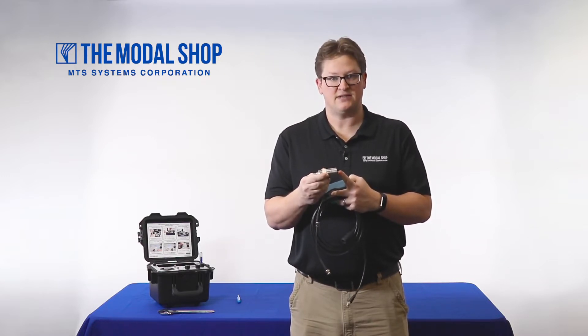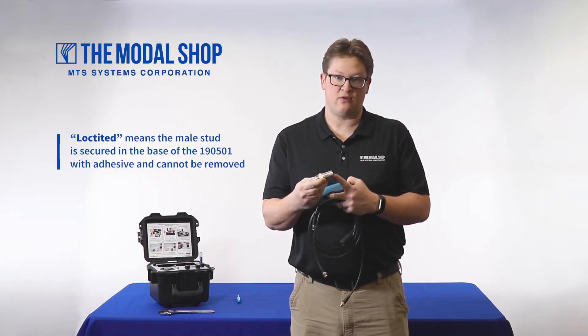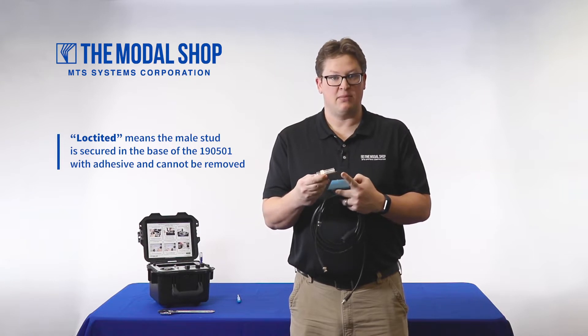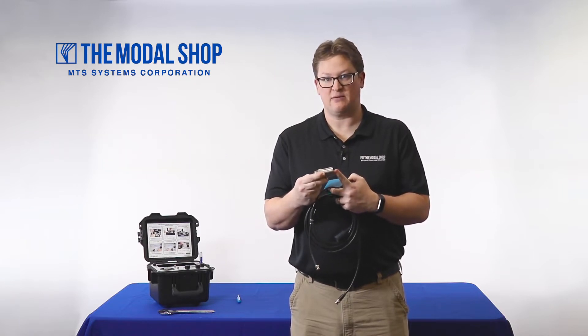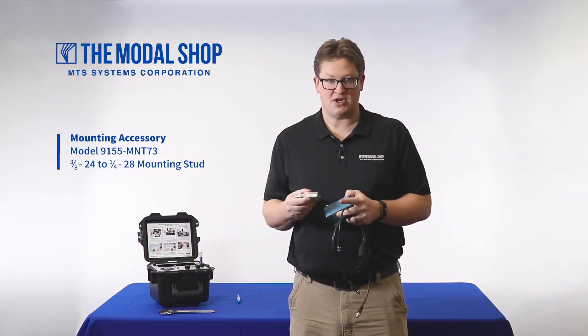As long as the stud is not Loctited into the bottom, we don't have to worry about it — we have a 3/8-24 to 1/4-28 mounting stud. But if the stud is Loctited into the bottom of the transducer, we'll want to get the appropriate female mounting adapter for the vibration shaker table.